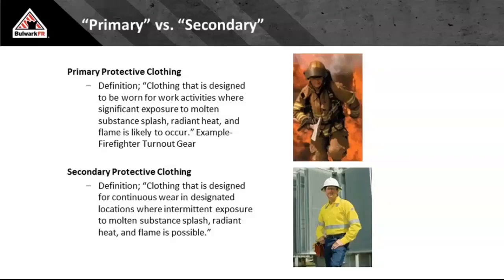It is task-based. Why? I am knowingly going into a thermal event. In our world, in the industrial environment, whether it's an arc flash or a flash fire, when do we need to have our secondary PPE on? All the time. Why? These are accidental events. We are not knowingly going into a thermal event. We are protecting ourselves if something goes wrong.